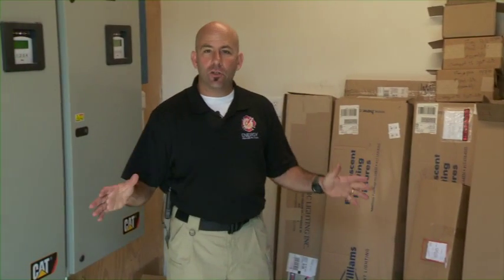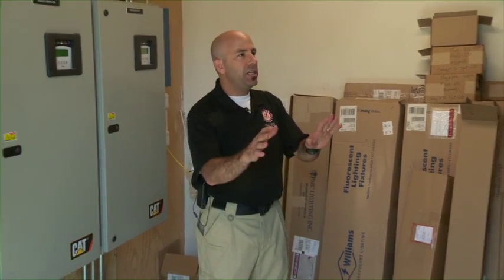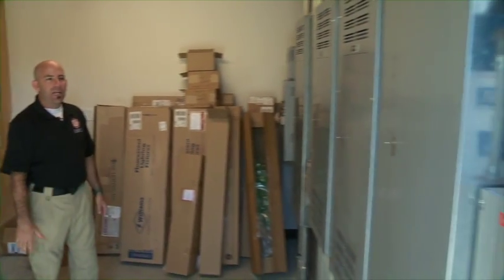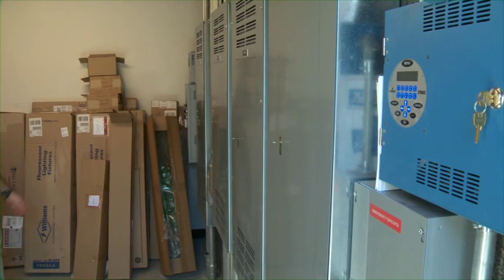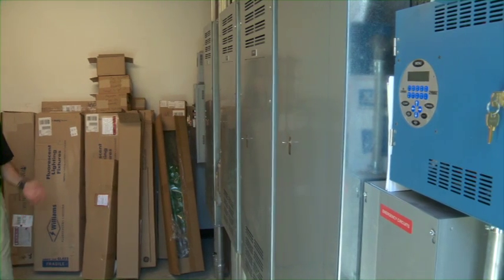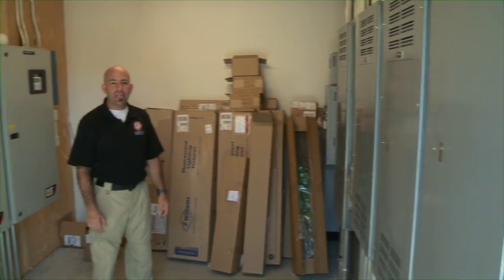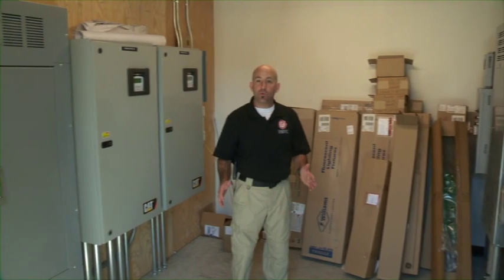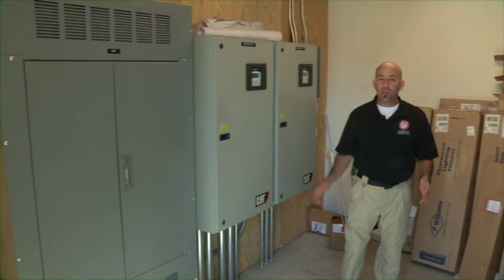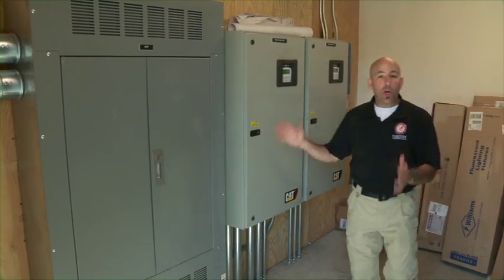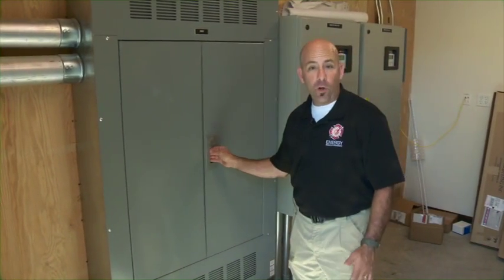Now we're in the main electrical room for this building, and you can see all of the panels in here handling all the individual circuits within the building. You can also see there's no labeling that says photovoltaic system in here. So if this is a room that we got to first, it could be a little confusing. Go to the largest panel because we want to shut down the whole building.